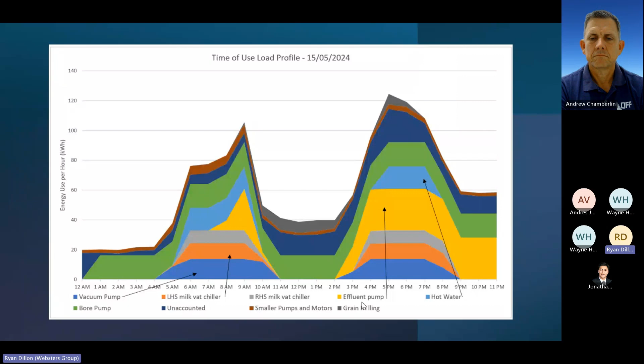Now it's running 24 hours a day, and if we hadn't attached the motor runtime counter, we mightn't have been able to detect this. But in this instance, as you can see, that's a $20 standard timer. We turn off the pump that's running, that's basically just feeding a leak, an underground leak in the supply pipework. And 50,000 kilowatt hours a year later, and $13,200 worth of savings just for a $20 timer, because we monitored and went to this level of granular detail. And it's effectively exposing things that might be invisible.